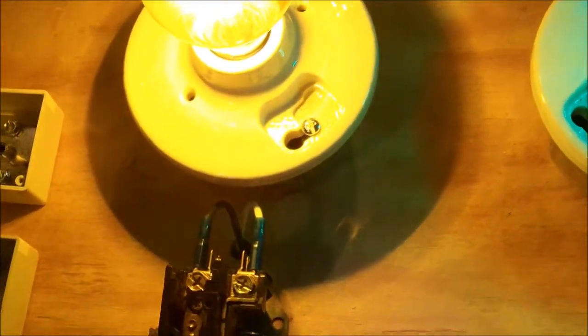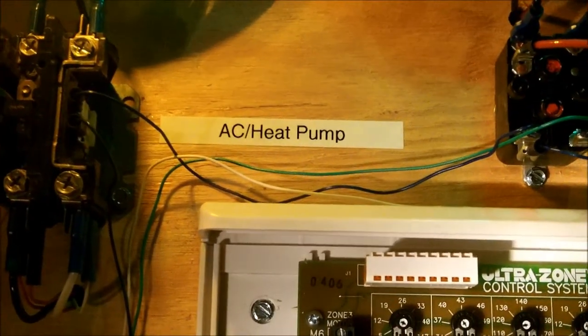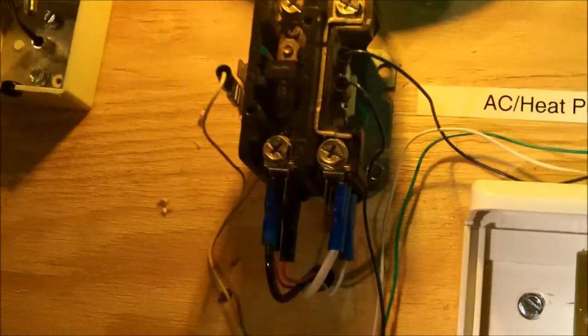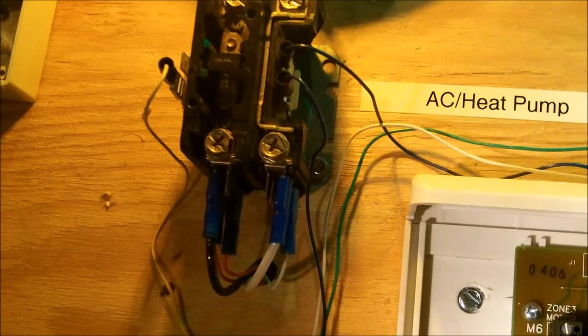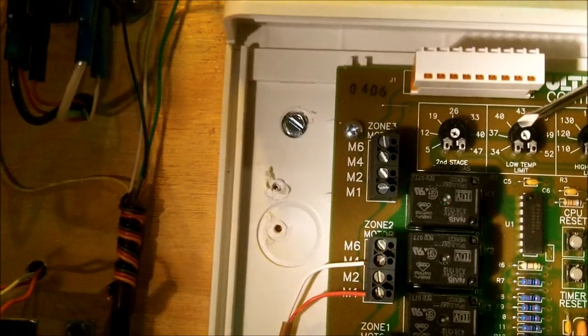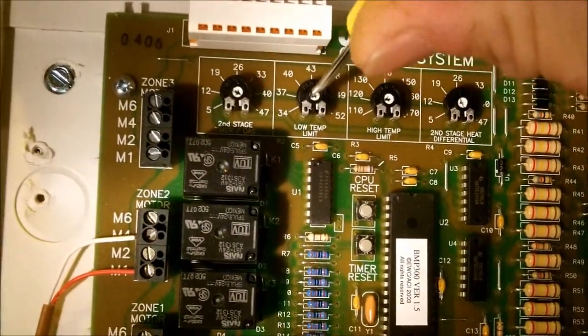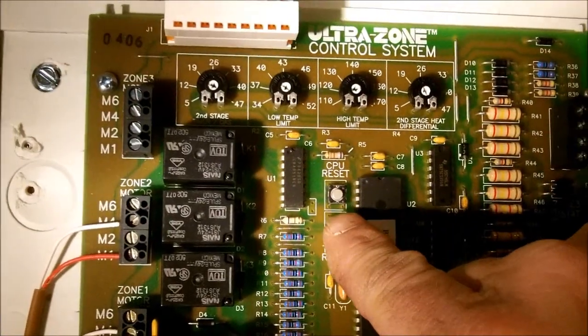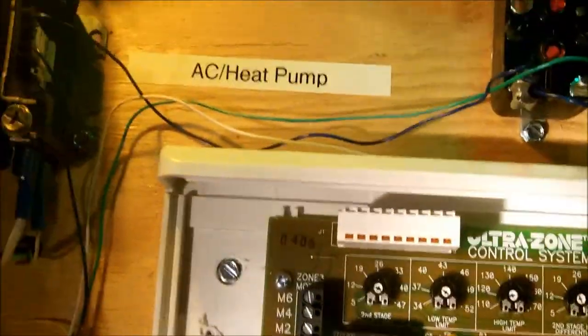Okay, my blower motor is on, just came on, so it's going to go through its 90-second purge. So anyway, it sends power. Alright, so it just went through a 90-second purge. The air conditioner is now on, and the blower motor is on. Alright, so while we're doing that, my low limit is at 40. So actually I want to turn that up. Let me turn it up here to like 52. We'll reset it. We'll do a timer reset. Alright, so there you go. See how fast that was? So if you're working on the thing in the field, that timer reset is always good.